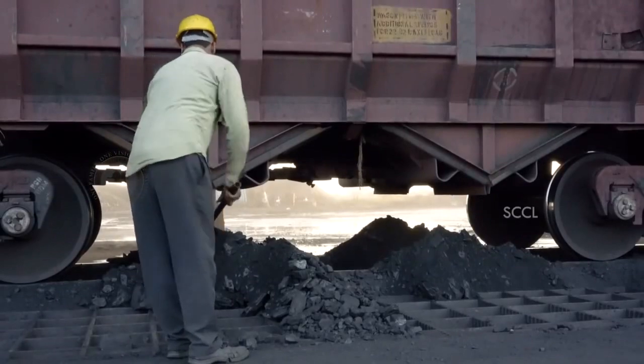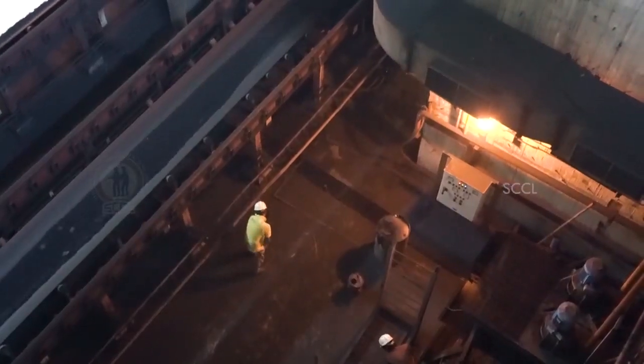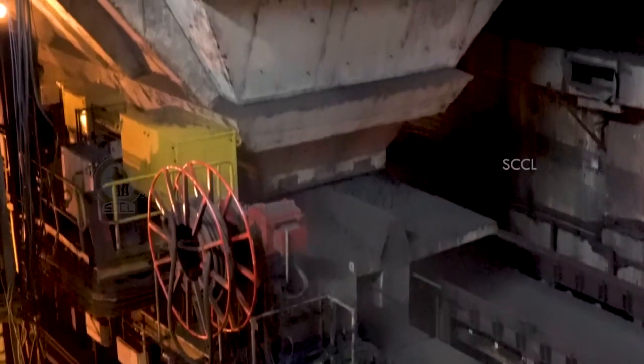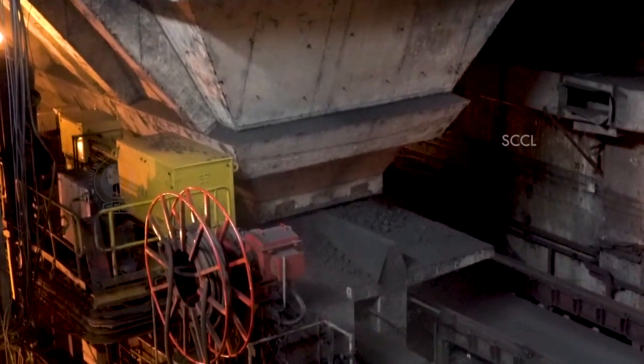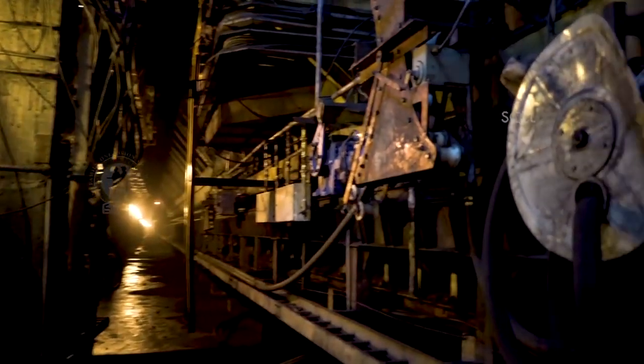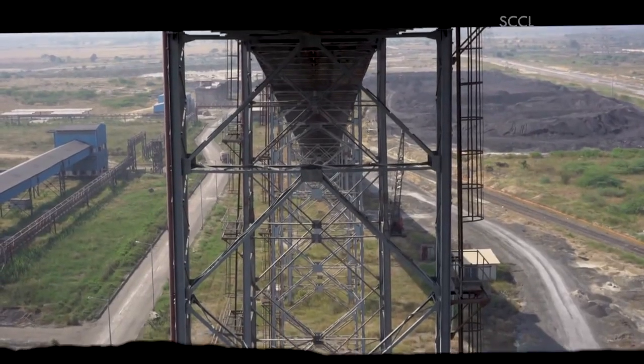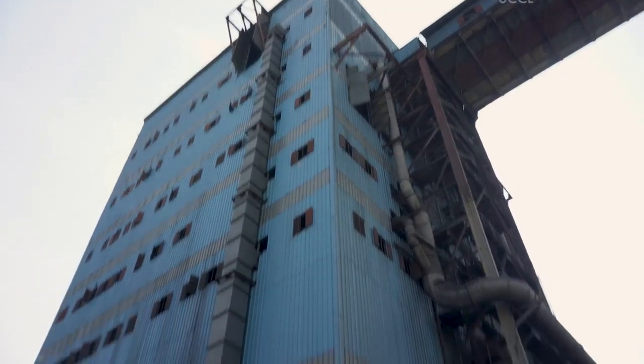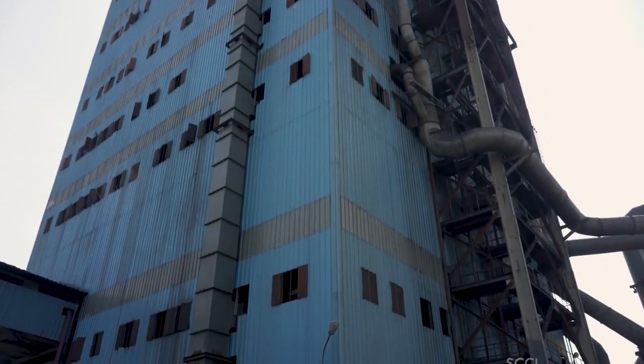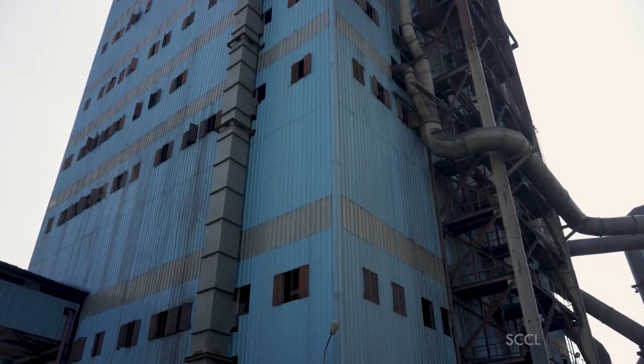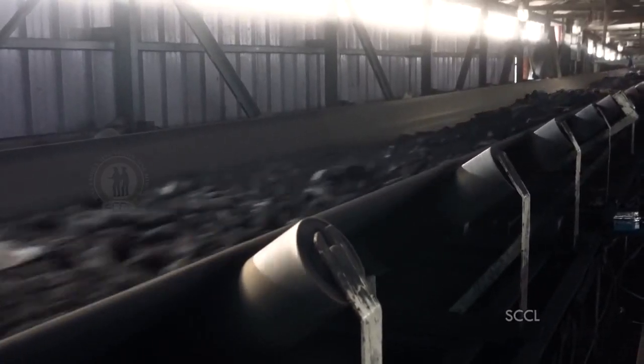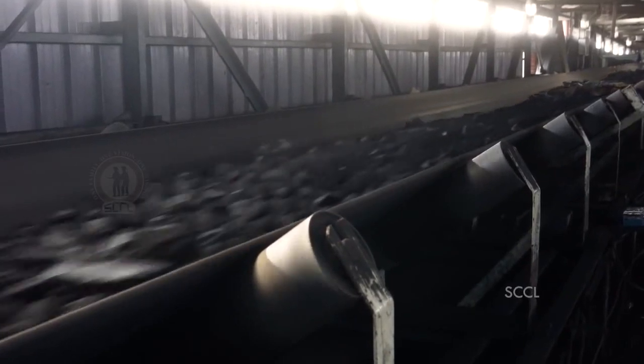These rakes are unloaded onto a track hopper, which is having underground bunkers with 6,000 metric tons of capacity. The coal is then scooped onto a belt conveyor that can transport up to 1,400 tons of coal per hour into the crusher houses, where raw coal of about 200 mm size is crushed into 20 mm size and is conveyed through various conveyors into the boiler feeder bunkers.